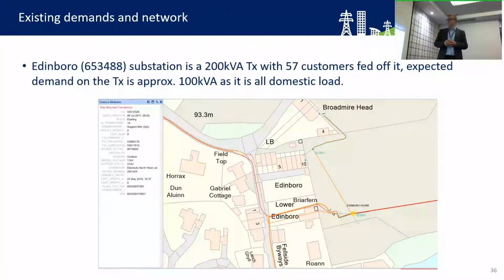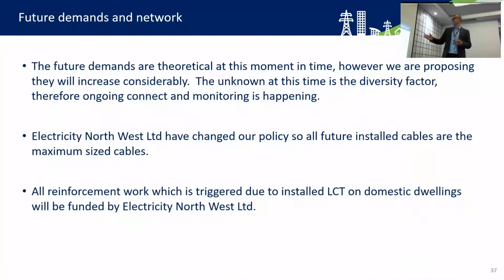So what we're saying is a lot of these future demands are theoretical at the moment, but going back to Jonny's slides, the demand increase is definite - it's inevitable that it's going to happen. The diversity factor at the moment is a little bit unknown. However, we've got lots of energy suppliers now saying they'll give you an EV tariff and you'll put your EV on between 10 o'clock and 2 o'clock or 4 o'clock and 6 o'clock. Some are looking at minimum system demand and switching car chargers on to try and work smarter, so it's almost a flexible connection, as we've mentioned.